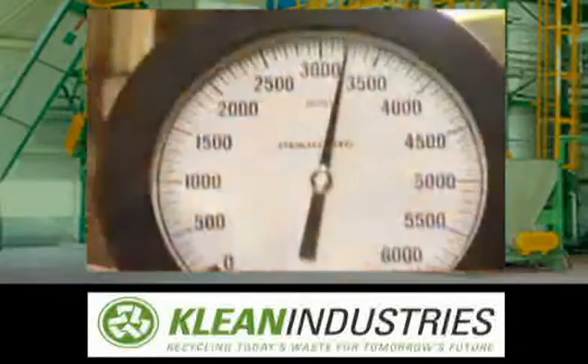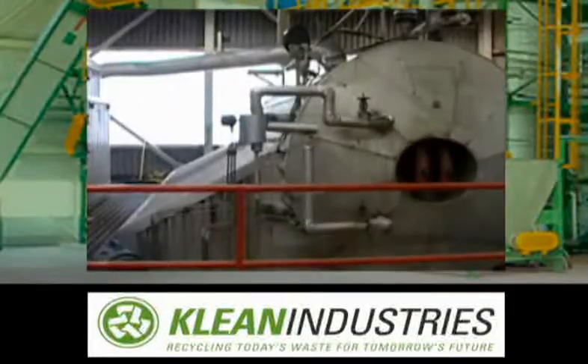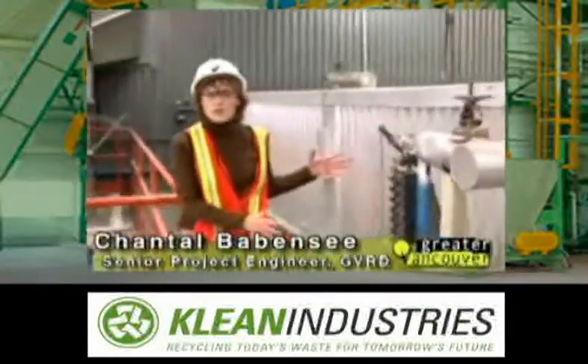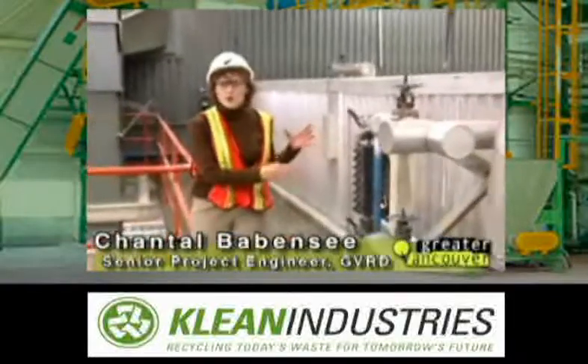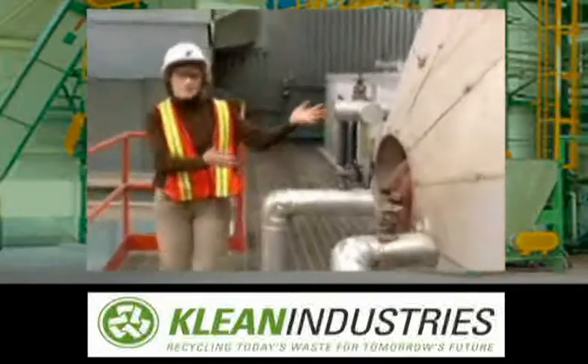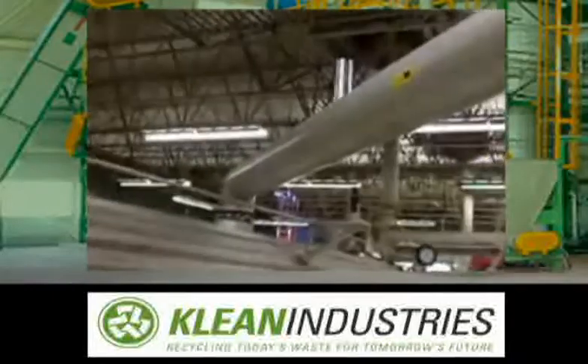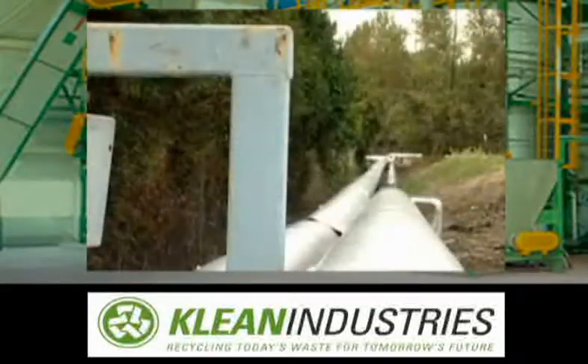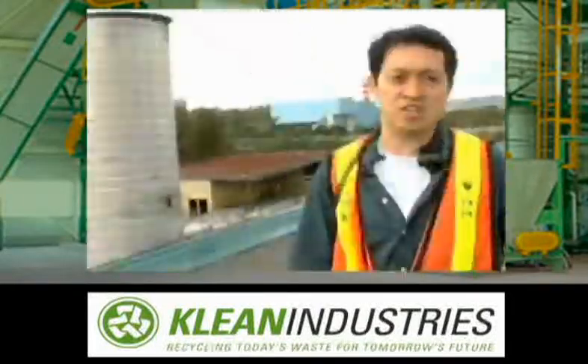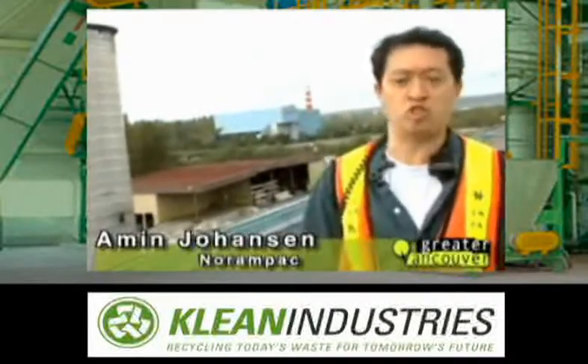The heat generated by the burning garbage is turned into steam. This is the very top of the boiler house — seven floors below is where the actual burn takes place. Within the boiler and furnace there are tubes filled with water. The heat from the fire creates steam within these tubes, collected in the steam drum right here. The steam is then piped over to the adjacent paper mill. After the steam is used, the condensate is returned back to GVRD to make steam again — it's a closed loop system.